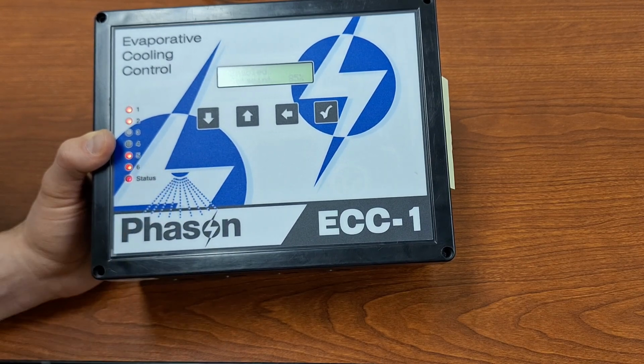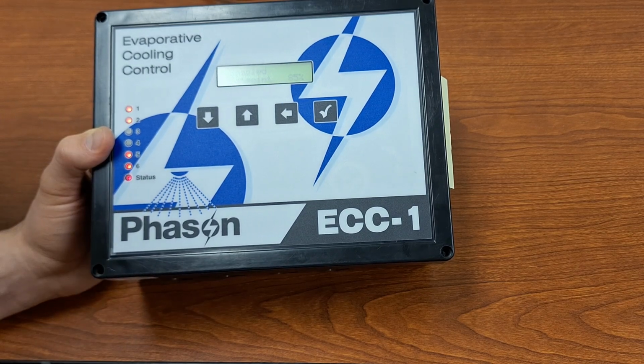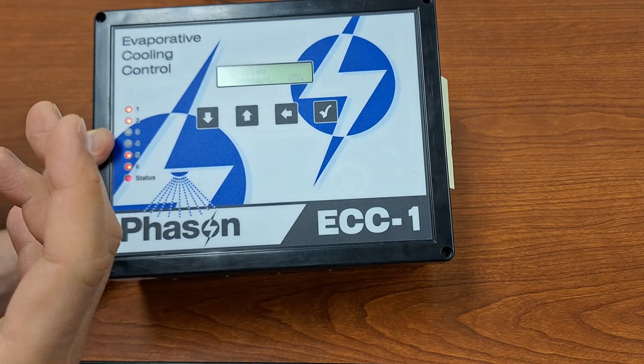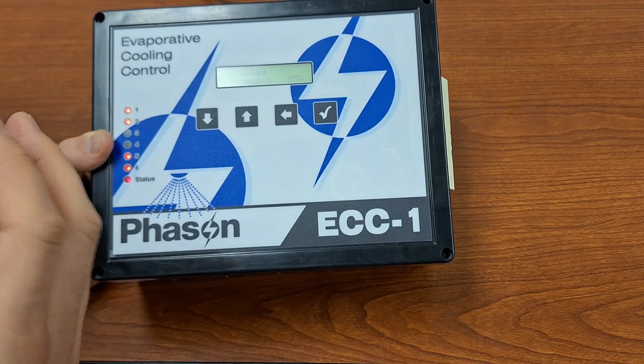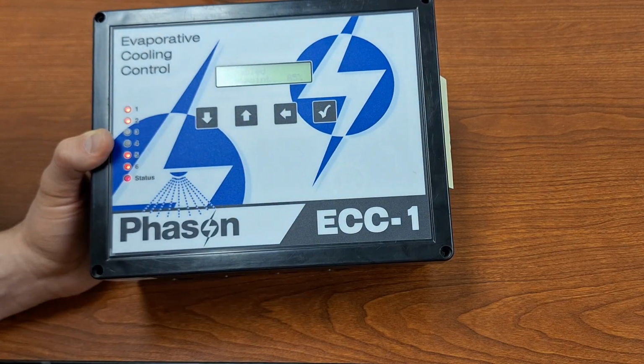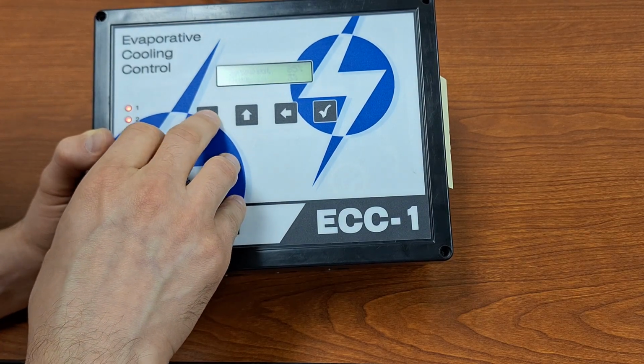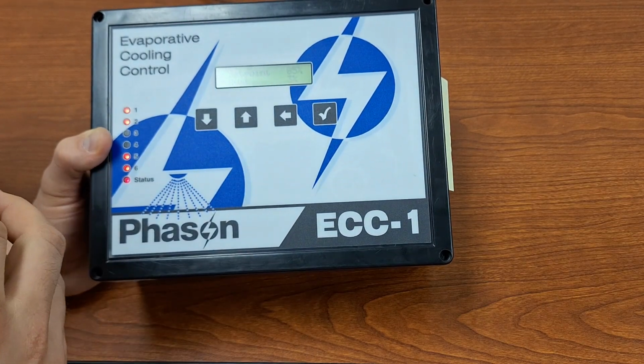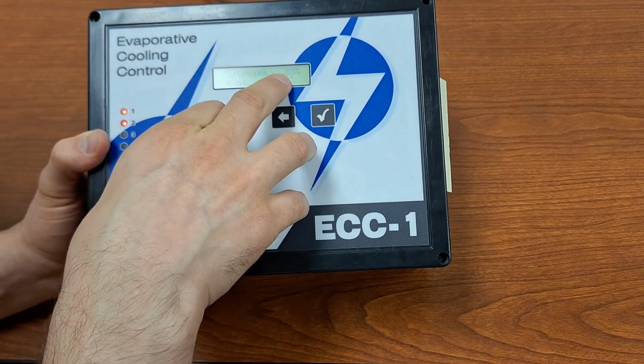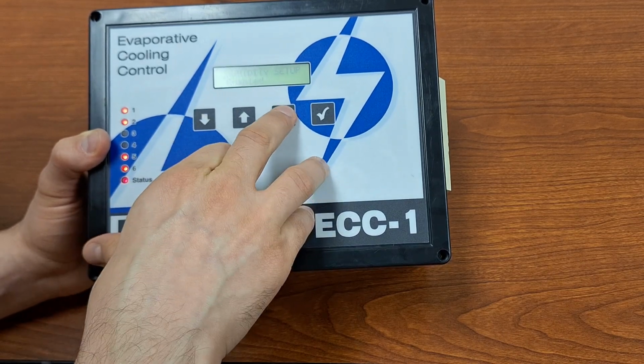And so this allows you to not add extra humidity, extra water to an environment where it's already very humid and you just need those fans running to hopefully try and evaporate and cool things down. And obviously you can adjust that set point to a setting that works well for you. And again, hysteresis, you can set that to what you want it to be. And this one, because we're working in percentages, is a percentage.